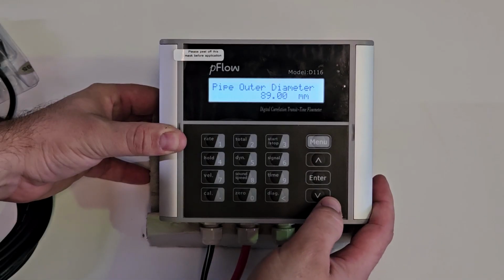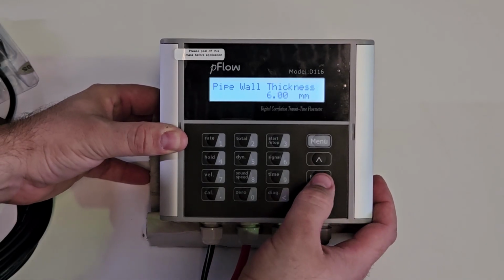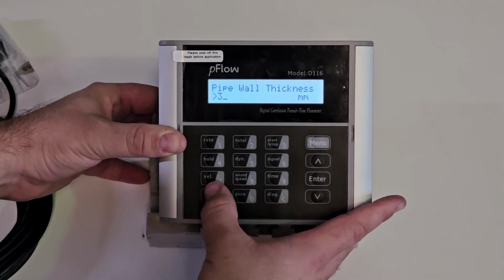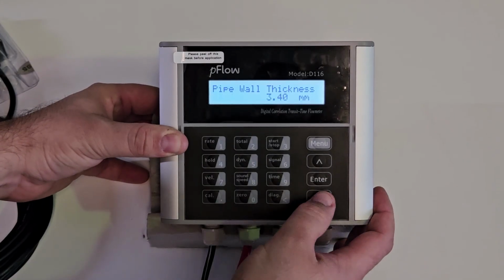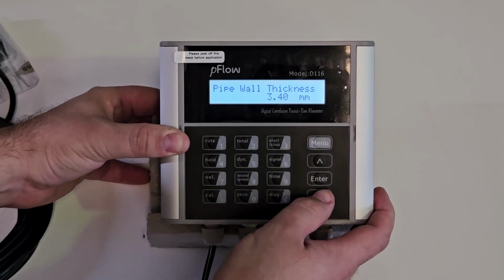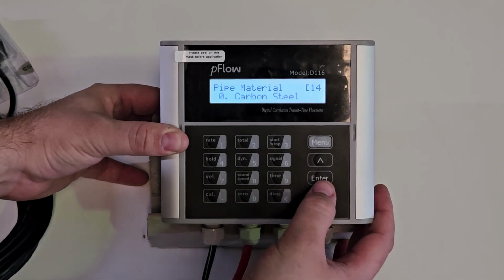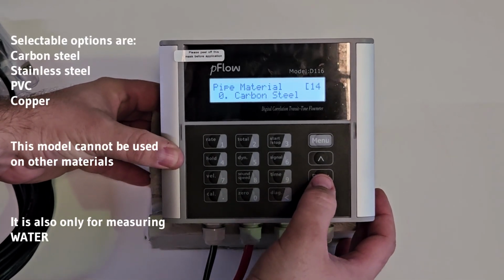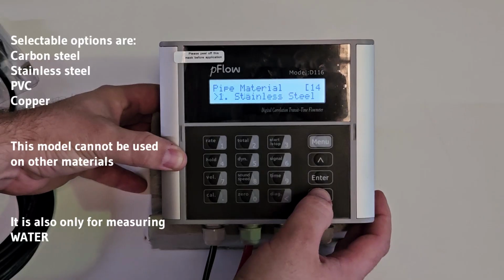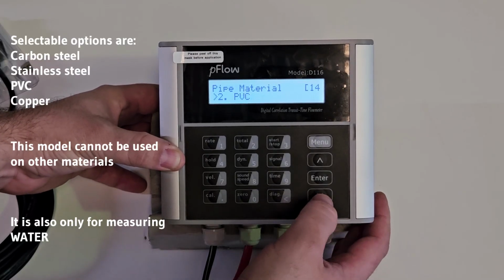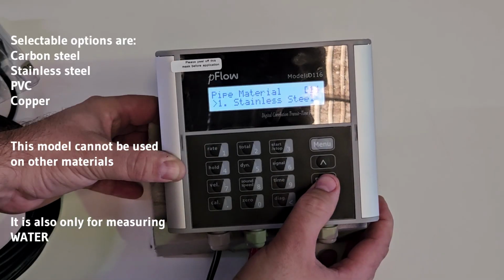Next press down, then enter again. Now enter the pipe wall thickness, which I have entered 3.4 mm in this case, then enter to confirm. Press down again to reach the pipe material setting. Press enter and then you can scroll the list of available materials with the up and down keys. In this case, I will choose stainless steel and press enter to confirm.